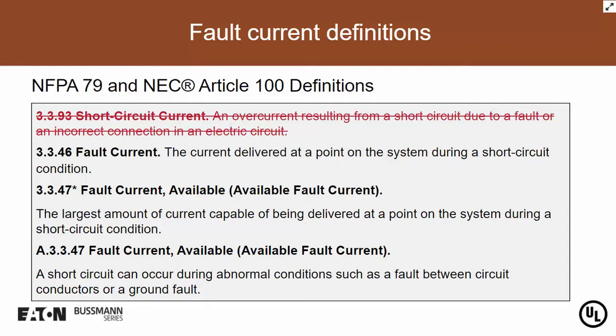Fault current is now the current delivered at a point on the system during a short circuit condition, whereas fault current available, or available fault current, is the largest amount of current capable of being delivered at a point on the system during a short circuit condition. There is a subtle difference between the two. Fault current is basically the current that flows under a short circuit condition. So you can see we talk about a specific point on the system.